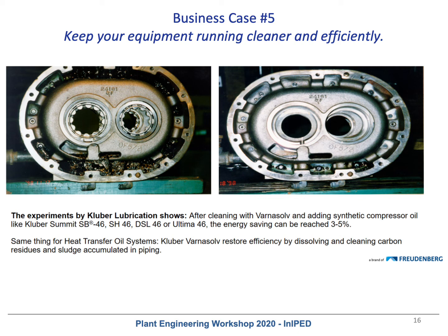Kluber has a special product called Kluber Varnasolv. We also have a Kluber Varnasolv HV, a high viscosity version for gearbox applications. But the regular Kluber Varnasolv is a cleaning and flushing agent, mostly used for compressors, hydraulic systems, and heat transfer oil systems. Normally you drain 10 to 15% of the content of the used oil actually running in the equipment, and you replace it with Varnasolv. You run the equipment as normal, with no need for disassembly, for a period of between 2 and 5 days.